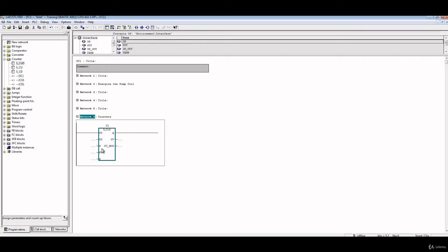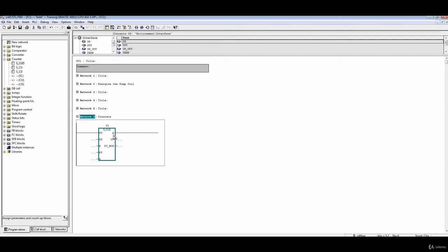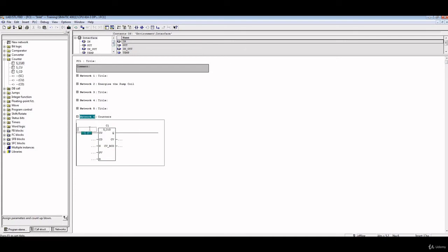You can set the value of CV if you put a boolean value on S. You can put the preset value of the counter here on the PV. And once that counter reaches this PV, the preset value, the value of Q will have a value of one. You can reset the counter if you put one on R, which is reset.